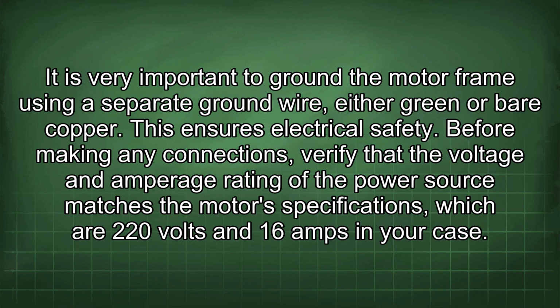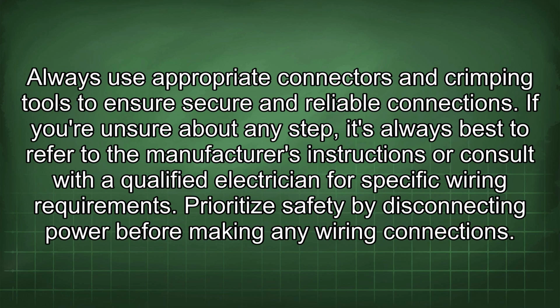It is very important to ground the motor frame using a separate ground wire, either green or bare copper. This ensures electrical safety. Before making any connections, verify that the voltage and amperage rating of the power source matches the motor's specifications, which are 220 volts and 16 amps in your case. Always use appropriate connectors and crimping tools to ensure secure and reliable connections. If you're unsure about any step, it's always best to refer to the manufacturer's instructions or consult with a qualified electrician for specific wiring requirements.